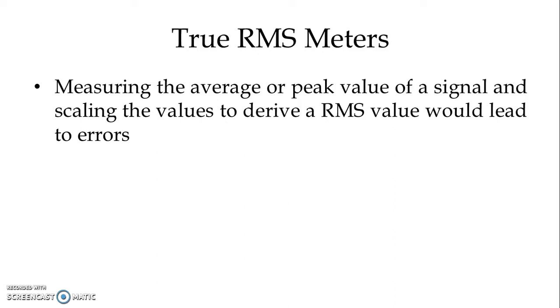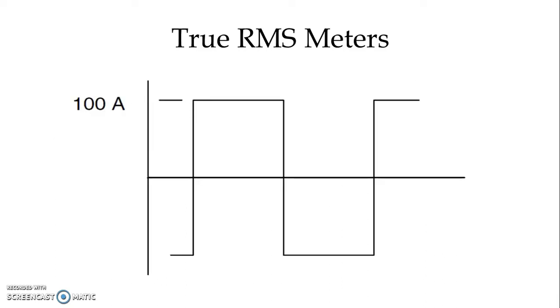But in the case of a harmonic-rich waveform, because of distortion, if we measure the average or peak value of a signal and then scale it down to the RMS value, it will definitely give the wrong value.